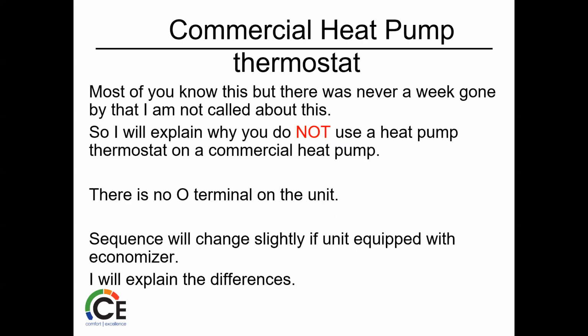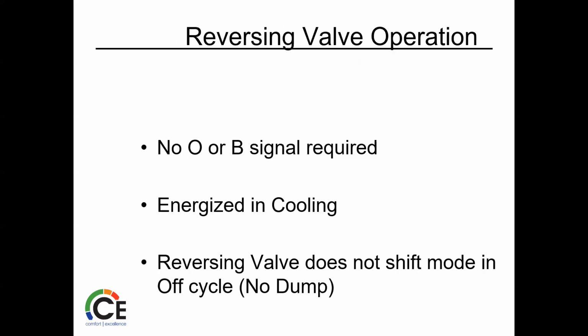Big thing here, I talked about that a little bit, no O on a commercial unit. The board takes care of that, all right? No O or B signal required. You know, B is the old way where Rheem used to send a B because they energized in cooling where everybody else energized in heating. This is energized in cooling. So again, that's backwards from what most residential guys see and gets them confused.